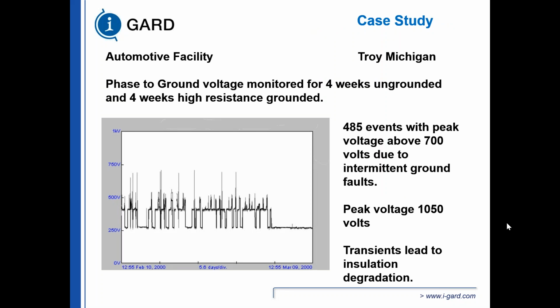Here's an example of an automotive facility that had 485 events of peak voltages above 700 volts due to intermittent ground faults, and peak voltages of 1050 volts. Transients lead to insulation degradation due to these escalating overvoltages. And we'll touch more upon this later.